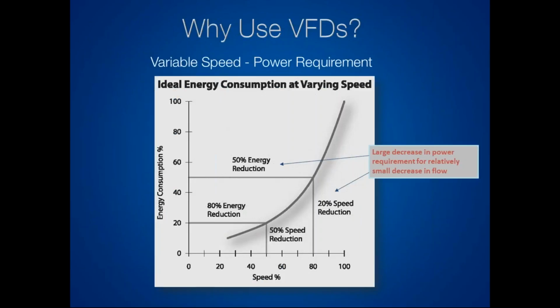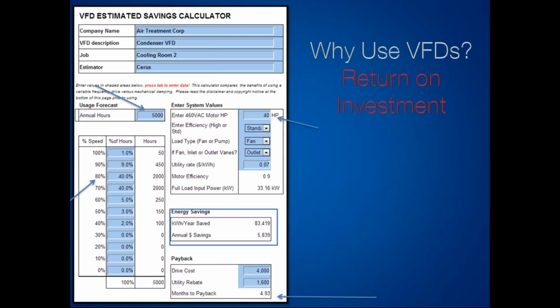So this is what I was talking about with the efficiency savings that you guys can expect to see. When we're running our motor across the line, 60 hertz, we're running it all out at 100%, we're letting that thing go, right? That's fine if you need to be running your motor at 100%. But a lot of the time, we don't need to run that motor at 100%, and so by turning your VFD completely on and letting that thing run at 100%, we're not acting as efficiently as we could be acting. So in a VFD's case, let's say we turn the speed down by 20%, okay? We take from running at 100% and we turn it down and we run it at 80%. We're going to see a 50% reduction in energy, okay? Let's say we turn the VFD down by 50%. We're going to see an 80% reduction in energy, okay? So it's really important to look at where your motor needs to be run and see some energy savings there.